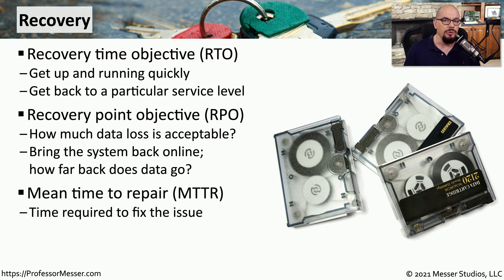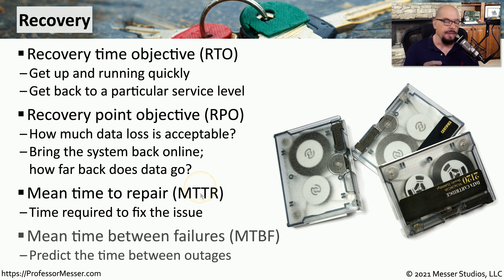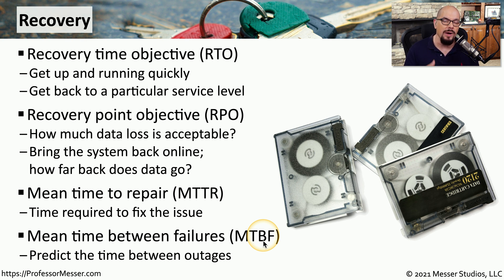If you're trying to understand how long it would normally take to make a particular repair, then you're looking for the MTTR, or the mean time to repair. This is a good estimate to help you understand how long it will take to get back up and running if there is an outage. Another important statistic is the mean time between failures, or the MTBF — if there is a failure, how long will it be before the next failure occurs? This is often useful so that you can plan to have the right resources in place at the right time to resolve these types of problems.